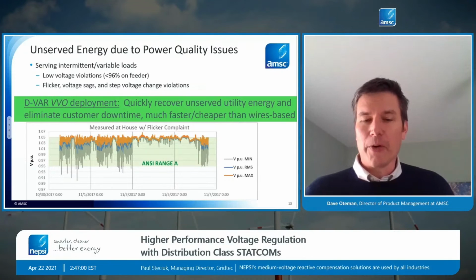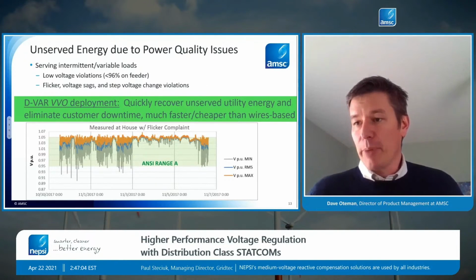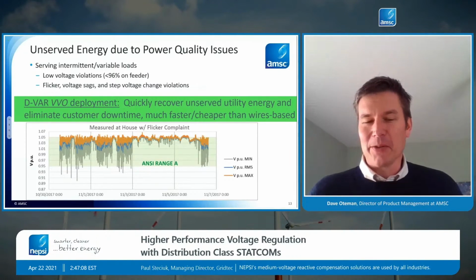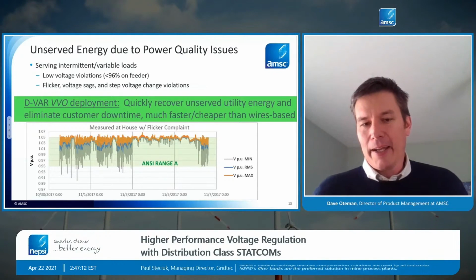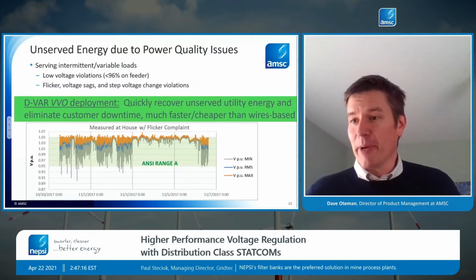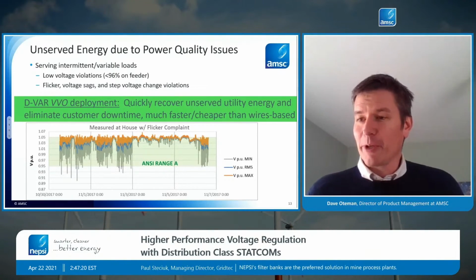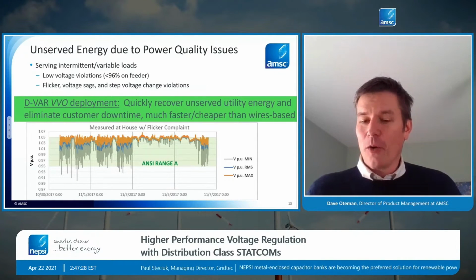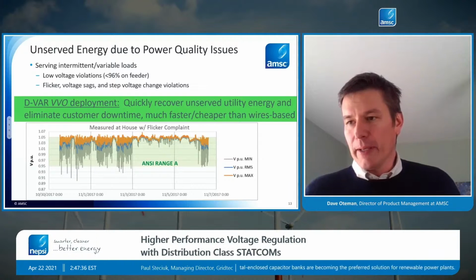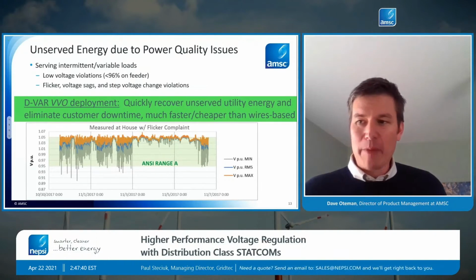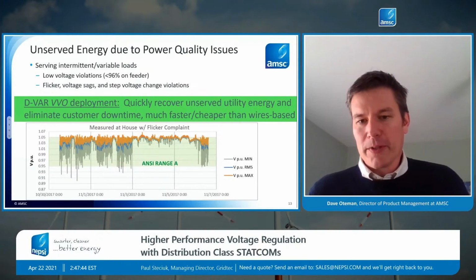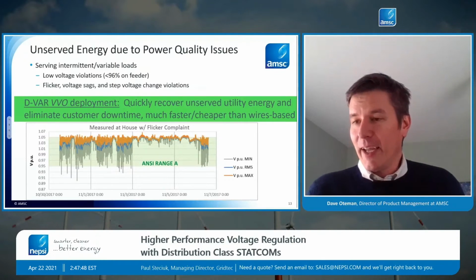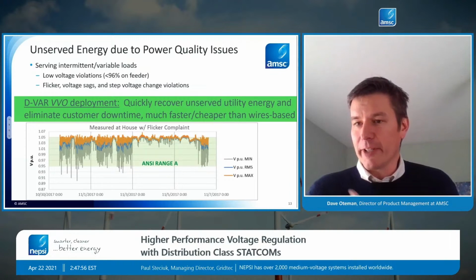The STATCOM is also able to directly address these types of power quality issues as an apparatus-based solution at much lower cost, much faster, allowing the industrial customer to get back online and the utility to serve that customer again—because whenever a customer is causing a power quality problem, they often have to curtail or even stop that process until it's fixed. Then the other customers are able to be served again with high service quality. So this is another good application for the technology, and it ties back to our initial eight problems we covered, six of which cannot be addressed today, whereas the STATCOM can address these very dynamic problems.